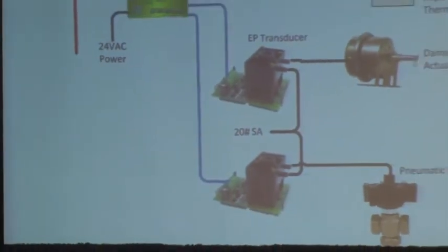And some of that is because of the valve actuators and damper actuators, if they're really big. Let's say you have a central plant with some large 6 or 12-inch valves, and they have some really big pneumatic actuators on those valves. To convert that to an electric valve could be very expensive. And if you've got a lot of them, that might be a reason why you want to keep those particular parts pneumatic. What you do then basically is you have a DDC controller with an electric to pressure transducer. The electric to pressure transducer takes that DDC signal output, which is going to be something like a 0 to 10 volt signal, and converts it. It does have to have 20-pound supply air brought to it, but then it has a pneumatic signal coming out to drive that pneumatic valve or damper actuator.